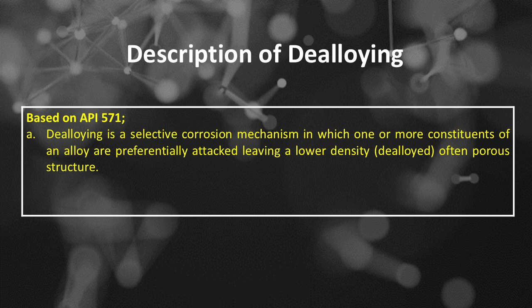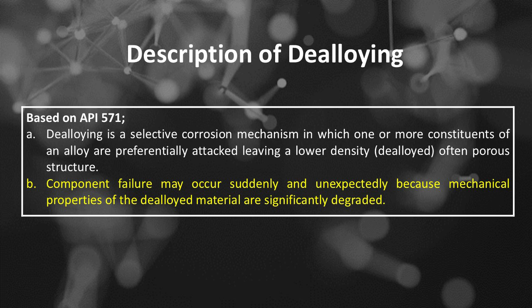Dealloying damage mechanisms are a part of uniform or localized loss of thickness. Description of dealloying based on API 571: Dealloying is a selective corrosion mechanism in which one or more constituents of an alloy are preferentially attacked, leaving a lower density, dealloyed, often porous structure. Component failure may occur suddenly and unexpectedly because mechanical properties of the dealloyed material are significantly degraded.